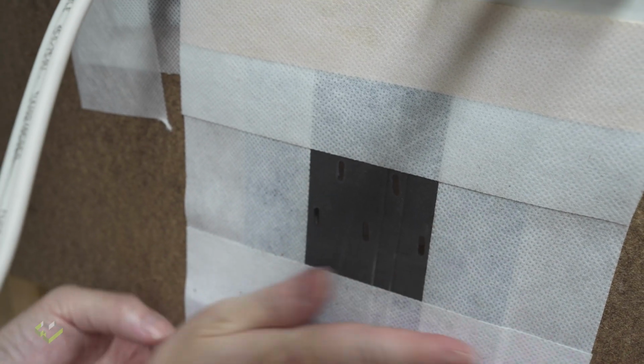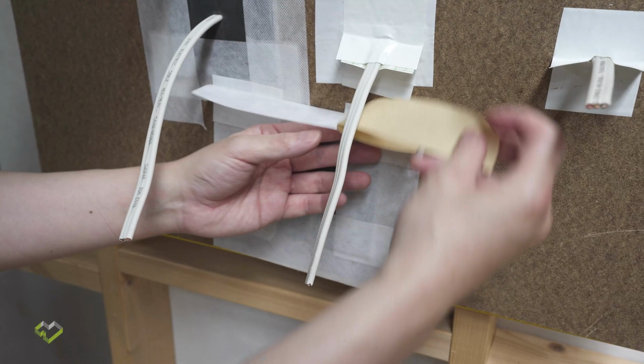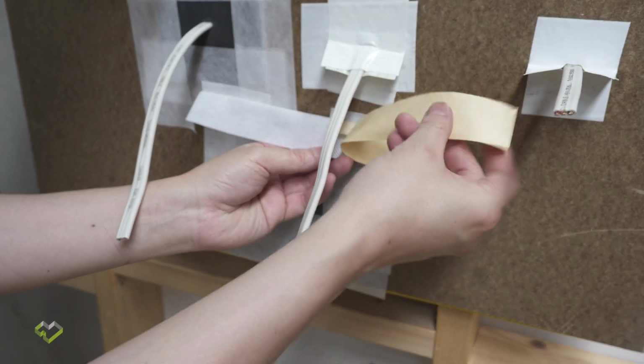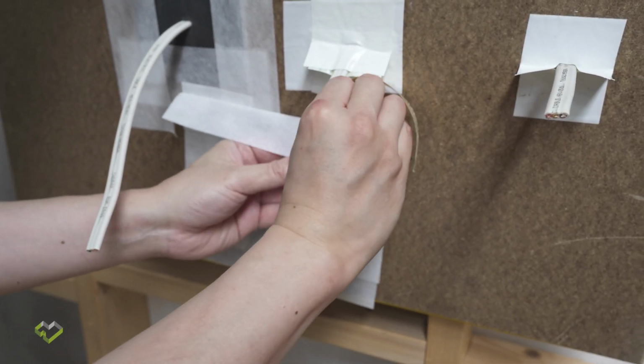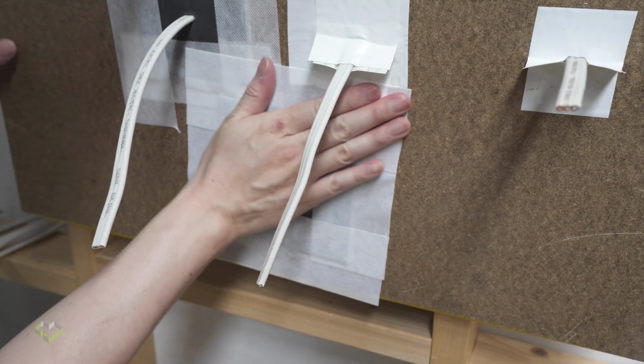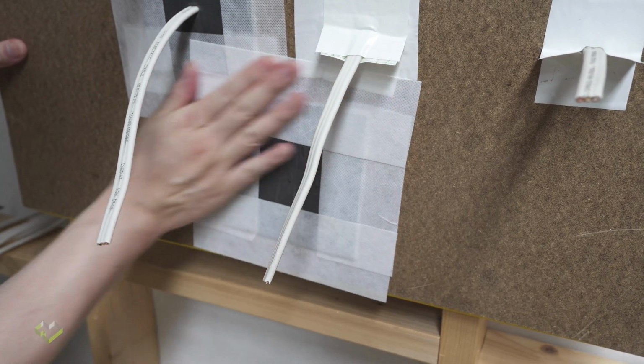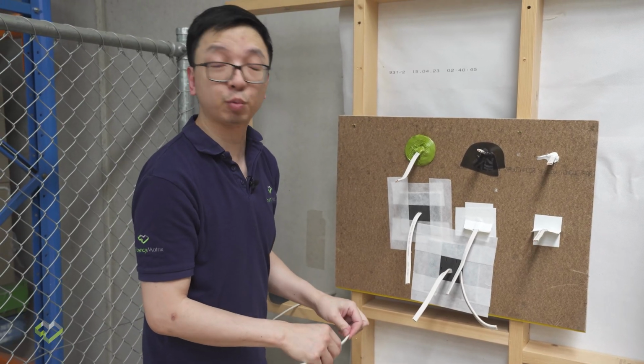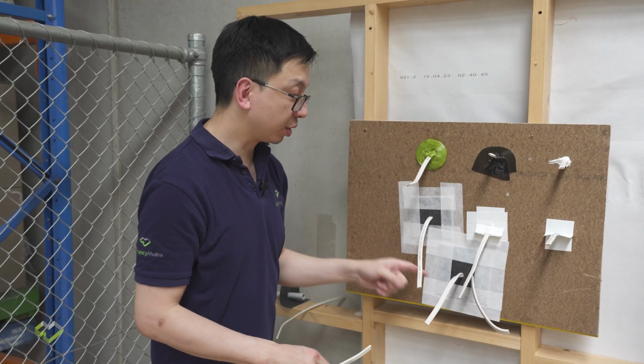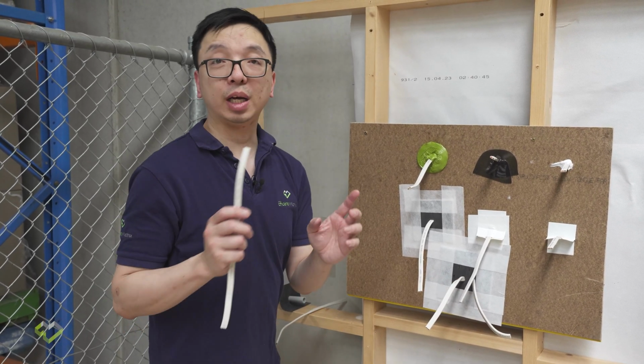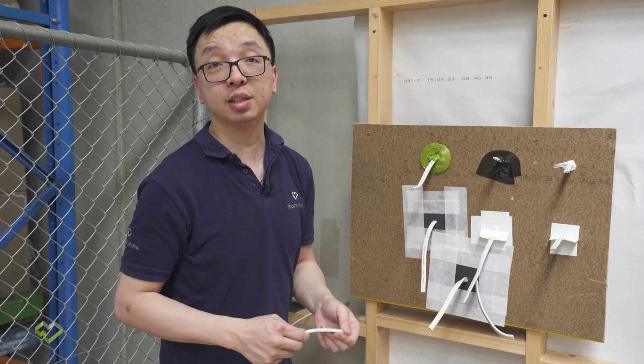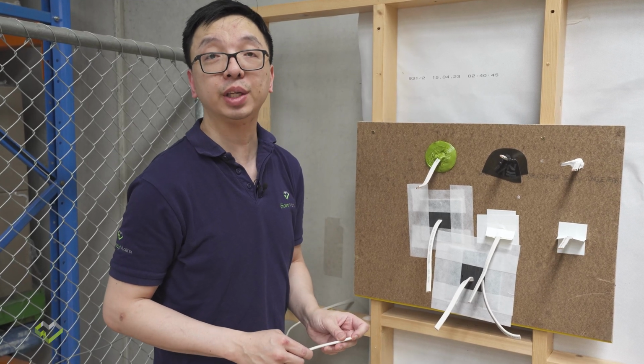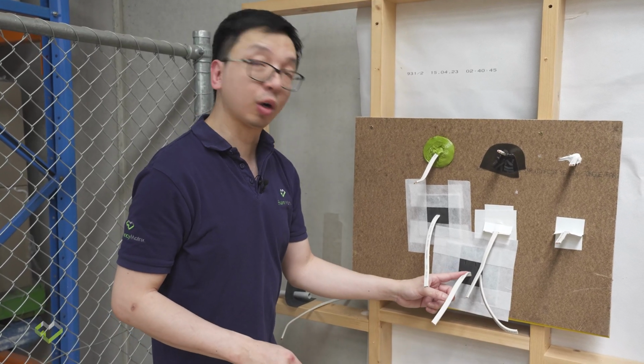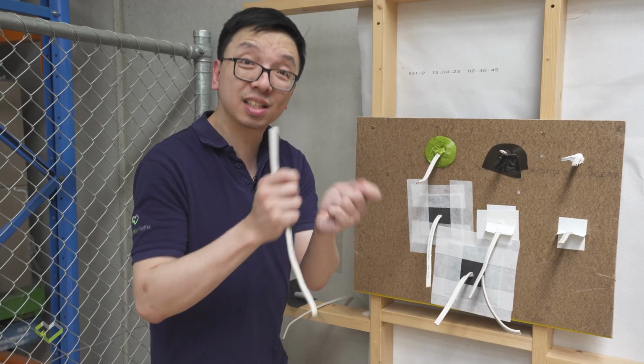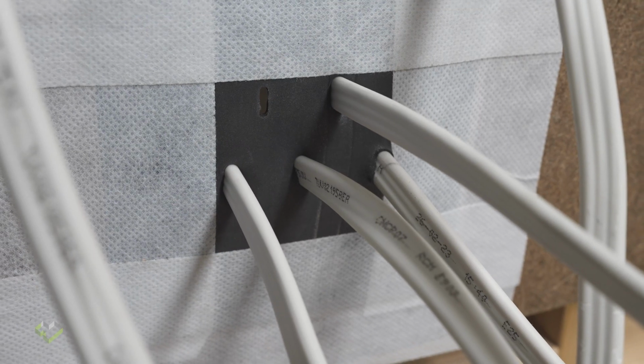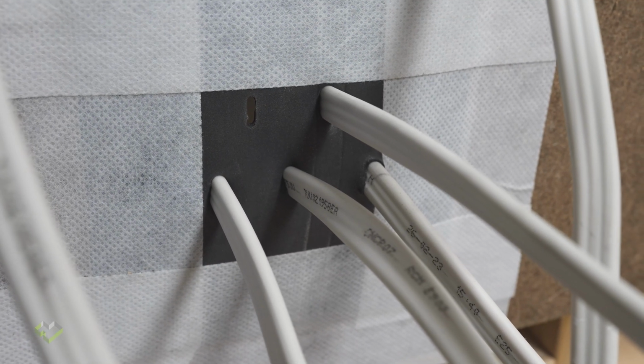Once the holes are properly aligned, we can release the remainder of the release liner and then fix it. And there is a special reminder when you're doing multiple holes with one gasket. Make sure between each hole, you got at least 15 millimeters, if not 25 millimeters gap. Otherwise, if the holes are too close together, it can easily tear. Looks like I'm one cable short, but we get the idea.